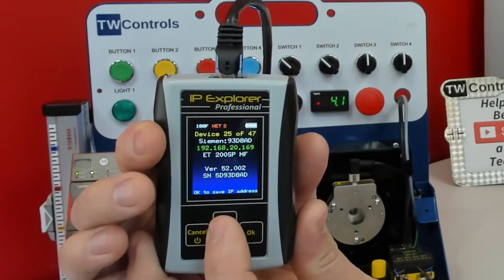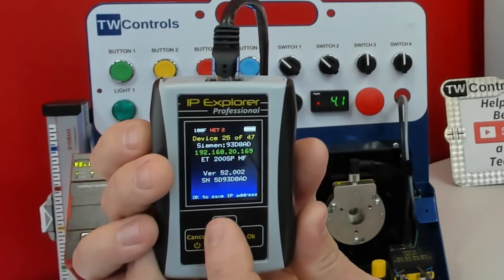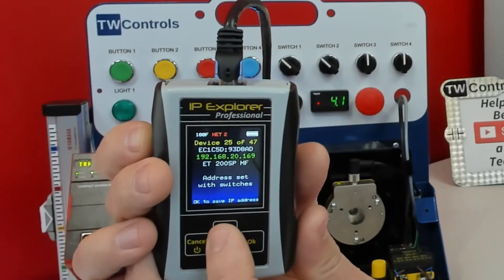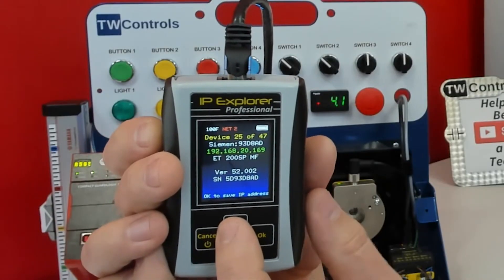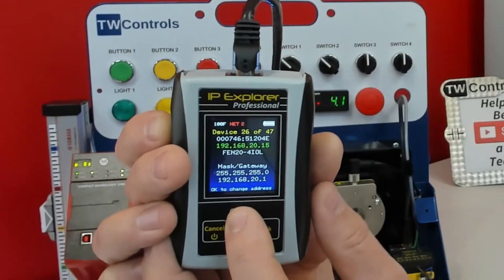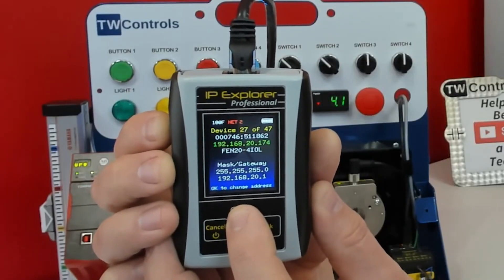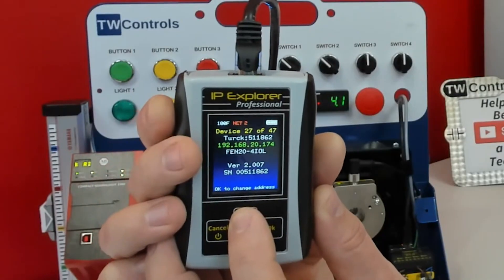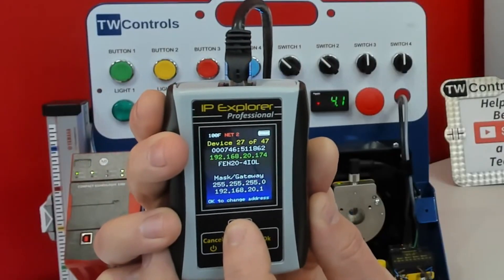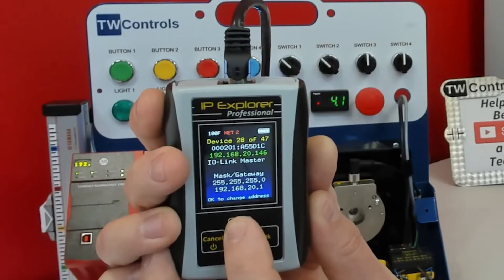This is a Siemens device — it's over Profinet. This is an ET200SP. Yes, I know Siemens people, you have Proneta, but you can't take Proneta and see Ethernet IP devices. There's a FEN20 — this is what a Turk IO-Link module looks like. It's only what they report, that's all we get. We can tell it's a Turk by the MAC, and then they just report their model number.